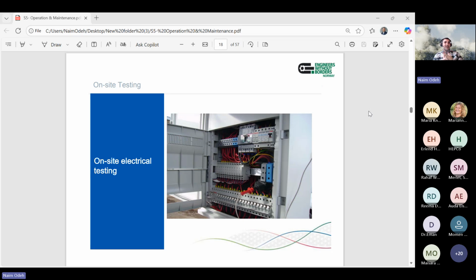All electrical equipment is installed in the right position. IP ratings for the enclosures and equipment are okay. So everything is there as it should be, and everything is matching the drawings submitted by the contractor or by the installer. If we reach this level, then we need to go to the next step. So we need to inspect the stuff that we cannot see by eye. We cannot visually inspect or verify them.